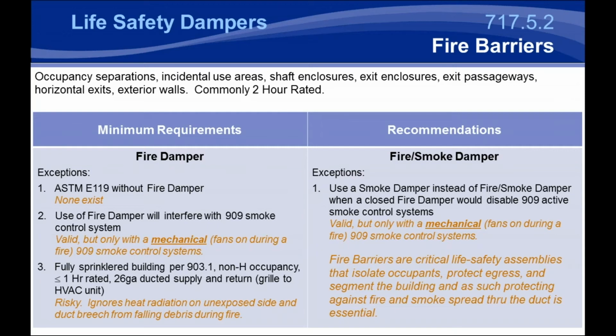They're either going to be active or passive, and the active ones are mechanical 909 smoke control systems. So they're using the fans to exhaust smoke out of the building or pressurize non-affected areas and create a little bit of a vacuum in affected areas. There are also passive 909 smoke control systems that basically shut down the building. They shut down the air handlers and close all the dampers as more of a containment. And of course, if that's the case, there's no way a fire damper is going to impede with that because there's no air flowing through the system.